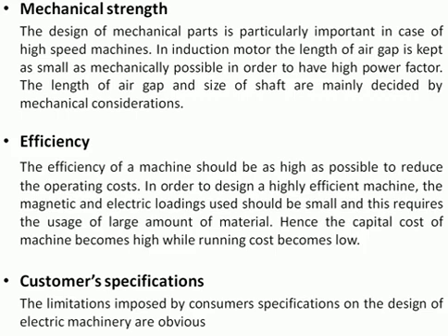So let's see the case of an induction motor. In the case of an induction motor, the limitation which comes into the picture is that you cannot design the machine with a very large air gap. Why? Because when the length of the air gap is large in an induction motor, its power factor will be very low, which is not a good characteristic of the machine.